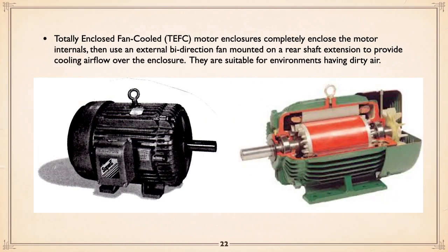If you take a look at the fan, that fan is tied to the motor speed, of course. And if the motor slows down, then the fan slows down. Now, on a centrifugal pump, that's not a big deal because the power varies as the cube of RPM. So as the motor slows down, the load on the motor driving the pump slows down. The pump load falls way off. So that little bit of cooling is just fine. You can run a centrifugal pump at whatever speed you feel happy with continuously on a drive. They will be happy. I know you hear stories, but no, they won't.